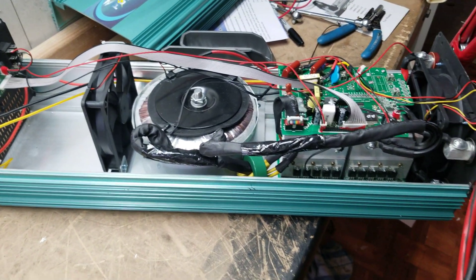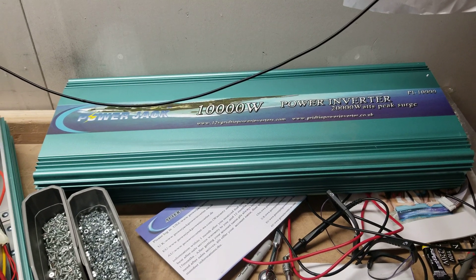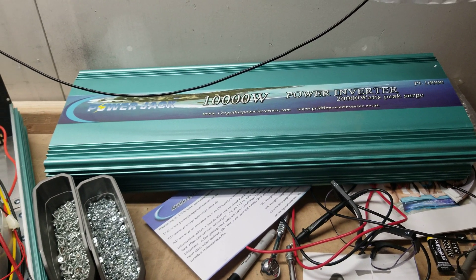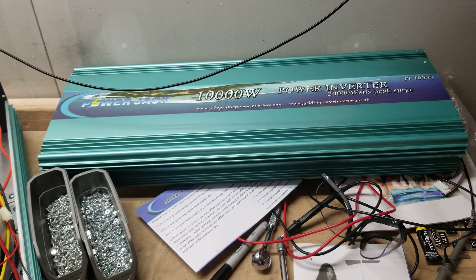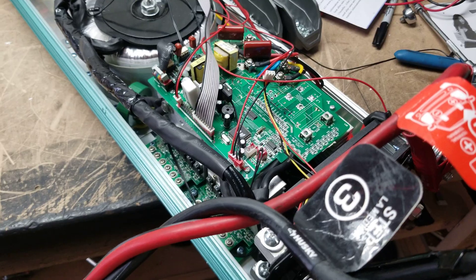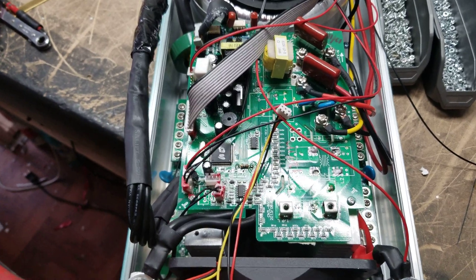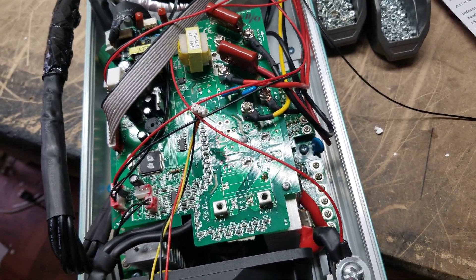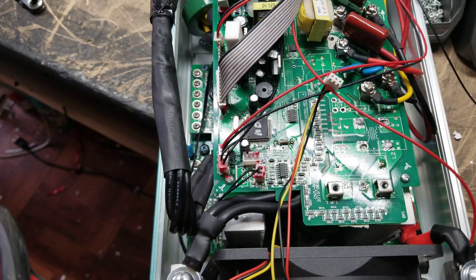This particular inverter is a 10,000 watt inverter from 2015. It uses the classic aluminum torpedo-style chassis. I am so glad they changed the design of the inside, because these things are a pain to actually get the main boards out and back in — they use insulators to keep the main board from shorting against the case, and getting all those insulators lined up is a pain.